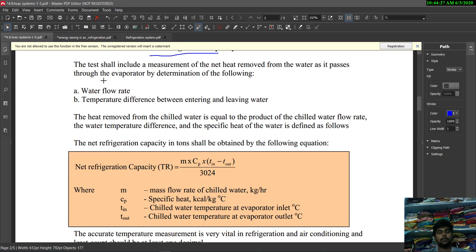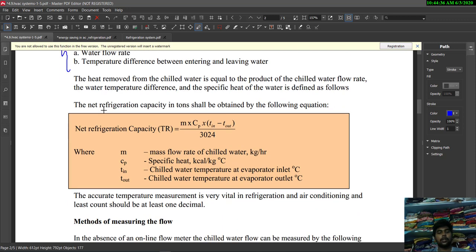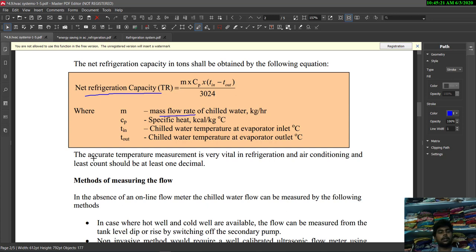To determine net refrigeration capacity, we measure the water flow rate and the temperature difference between entering and leaving water. The net refrigeration capacity (TR) is given by: TR = (mass flow rate of chilled water × specific heat × (T_in − T_out)) / 3024, where T_in is the chilled water temperature at evaporator inlet and T_out is at the evaporator outlet in degrees Celsius. Accurate temperature measurement is vital, and the least count should be at least one decimal place.